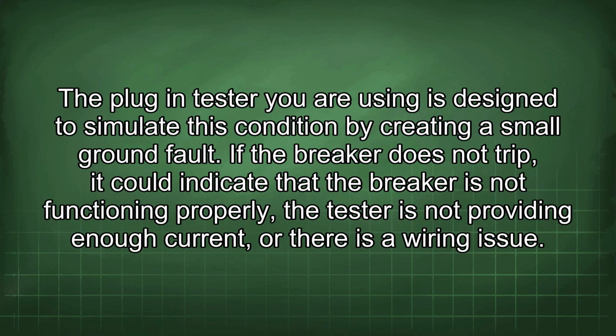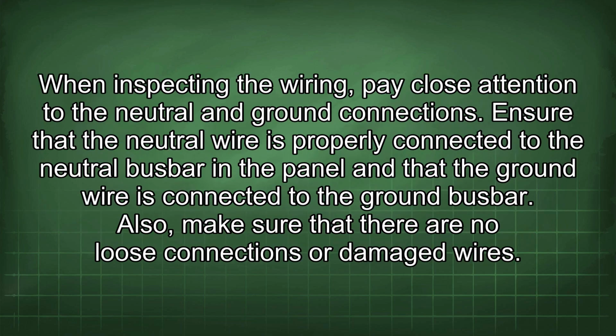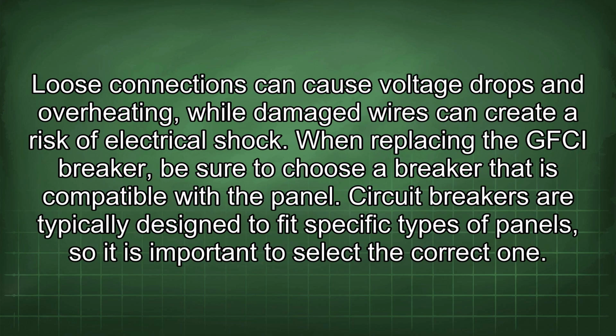The plug-in tester you are using is designed to simulate this condition by creating a small ground fault. If the breaker does not trip, it could indicate that the breaker is not functioning properly, the tester is not providing enough current, or there is a wiring issue. When inspecting the wiring, pay close attention to the neutral and ground connections. Ensure that the neutral wire is properly connected to the neutral busbar in the panel and that the ground wire is connected to the ground busbar. Also, make sure that there are no loose connections or damaged wires. Loose connections can cause voltage drops and overheating, while damaged wires can create a risk of electrical shock.